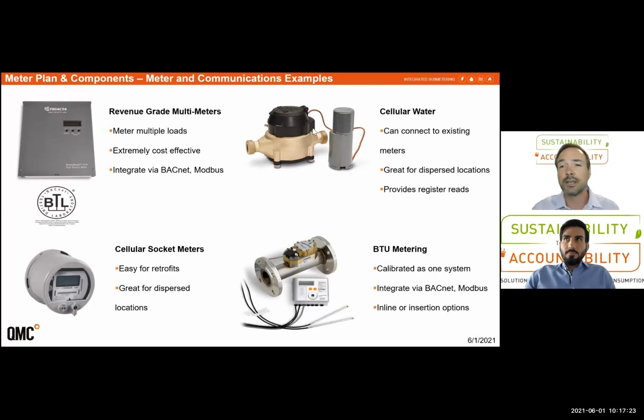And same with this cellular-enabled water meter where you have dispersed water meter requirements, such as irrigation, perhaps a few large tenants like a restaurant or a gym within a building. You're able to put these devices in and get 20 years of battery life out of communications without having to hardwire a solution. And lastly, just touching on BTU metering as well. Pete's going to talk about that in a few slides, and we wanted to touch on it because Measurement Canada is now regulating this technology, and it's much more prevalent in new buildings lately.